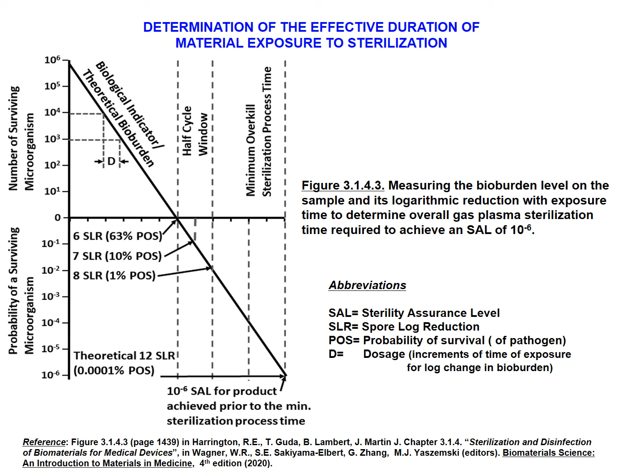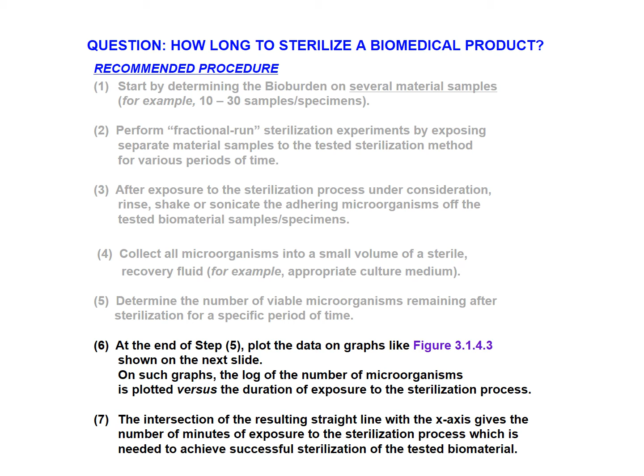Summarizing the results of this procedure, a reminder that the log of the number of microorganisms is plotted versus the duration of exposure to the sterilization process. The intersection of the resulting straight line with the x-axis gives us the number of minutes of exposure to the tested sterilization process, and this time interval is needed to achieve successful sterilization of the tested biomaterial.